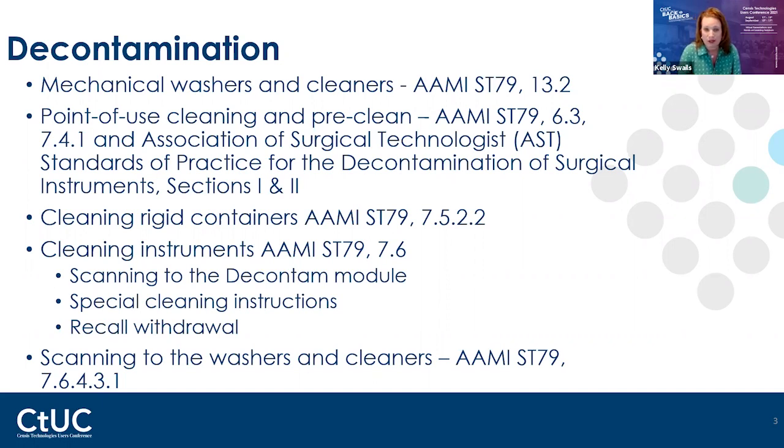Next on here, I have rigid containers. So rigid containers, when I'm on site and I see rigid containers, many times if you don't have a cart washer, I'm seeing that they're not being cleaned. So you can look at the IFU, you can look at AAMI guidelines. There's a little bit of controversy with some of those IFUs, but AAMI clearly states it should be cleaned before sterilization. So if your facility is taking those containers out of the room before the patient comes in, bringing them down to sterile processing, and then they're considered clean because they never had dirty instruments in them by a patient, and then they're just sitting there waiting for the basket, the instruments, to be washed and come back through.